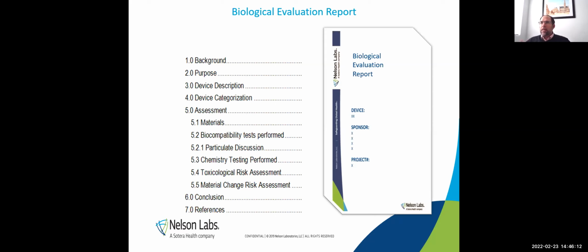Then the assessment, you're talking about the materials that you're using, what biocompatibility tests you performed, were there particulates generated that could have been an impact from the change. If you did any chemistry, what that tox risk assessment looks like, then the material change risk assessment from like an implantation standpoint or whatever, and then your conclusion.